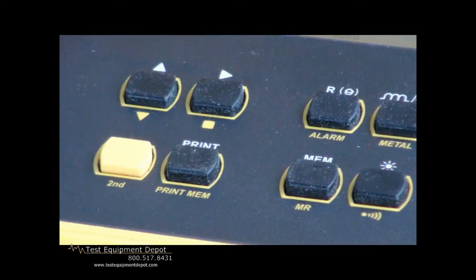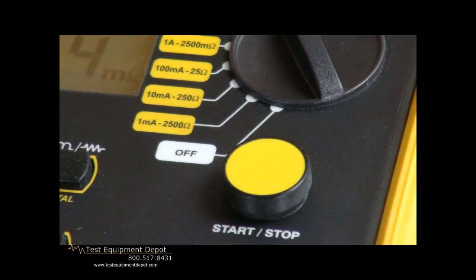That is why we have test currents available from 1 milliamp clear up to 10 amps. We're going to stress this bonding connection where two particular pieces of metal are touching, be it welded or be it a cinch down or torque down, a lug and a bus bar, for example, in the case of power wiring.